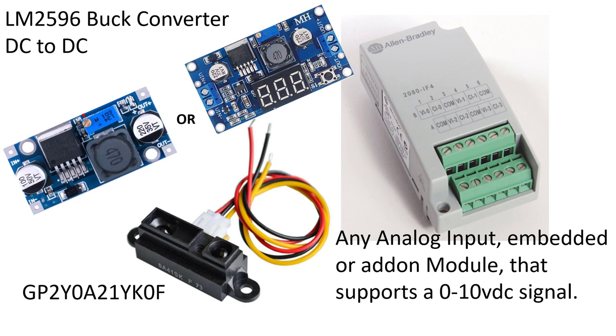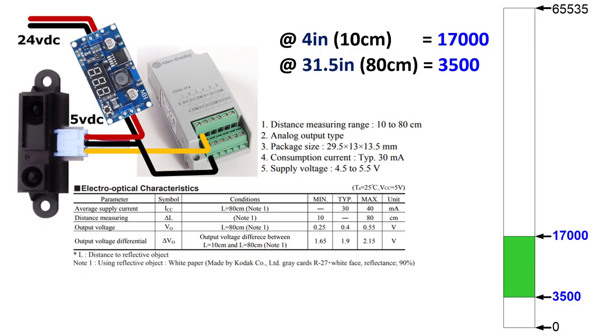You need 5 volts DC, you need this sensor, and you need any analog input embedded or add-on module that will support a zero to 10 volt DC signal. I'm going to use an IF-4 because that's what I have on my Micro 820. You can see how simple the wiring is there. 5 volts DC to the red wire, and then the black or common is shared between the DC supply and the common. Notice that IF-4 has voltage and current terminals, so you got to be careful what you're doing.